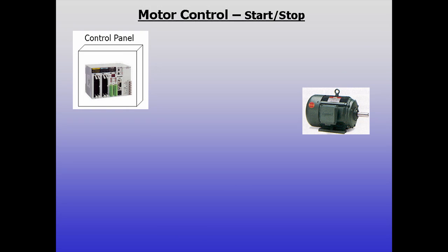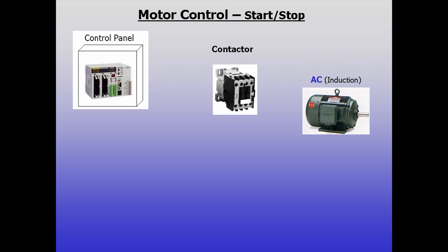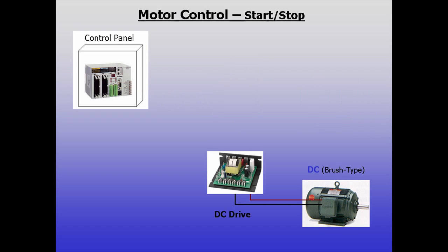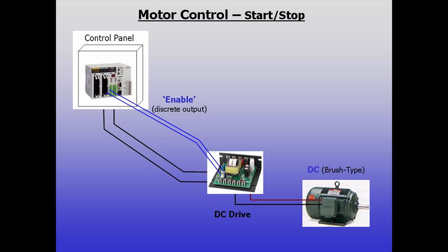The simplest control is on or off. This is common for motors that will only run at fixed speeds. For AC induction motors, discrete outputs can energize the coil of a contactor, which then passes full power to the motor. DC motors will require a DC drive to furnish their power, but it can also be triggered with discrete outputs.